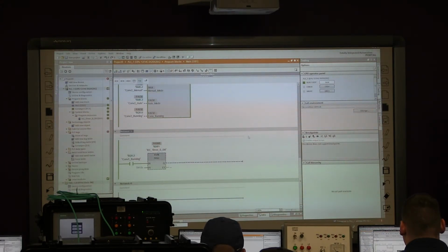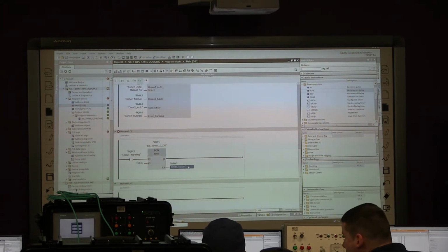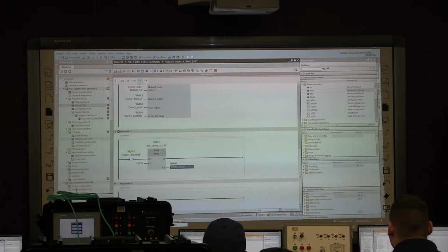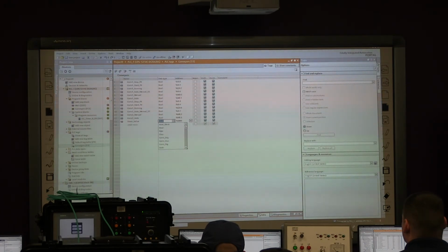Okay, gotta add it down here. Yeah, let's make it on the fly, because that might be timer value. What's it telling? The data type word of the actual parameter does not match the data type time, so it has to be a data type time instead of word. Make the data type time in that tag that we just made.